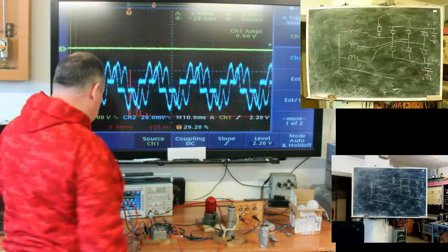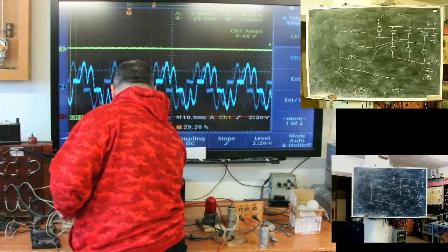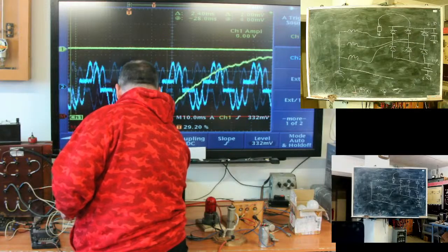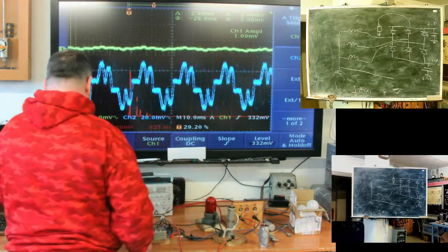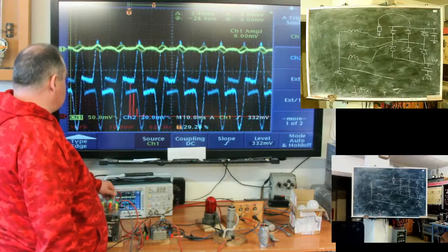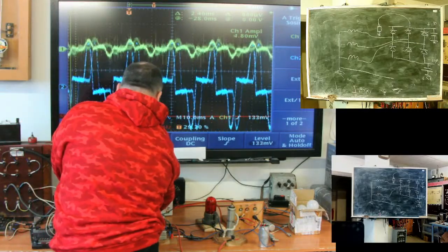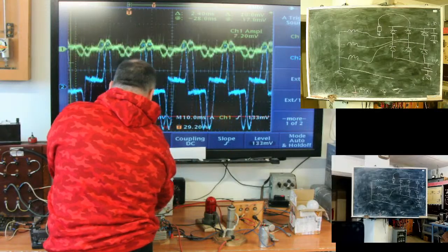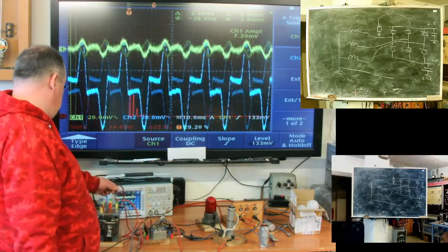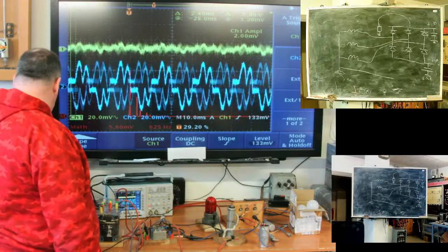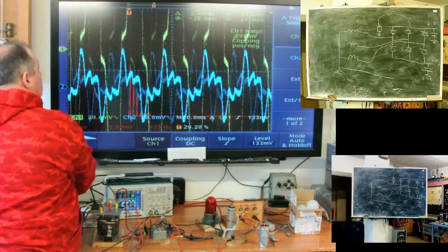And one moment, I will reconnect the ground wire. C phase disconnected on the secondary side. Small current. C phase disconnected on the primary side.